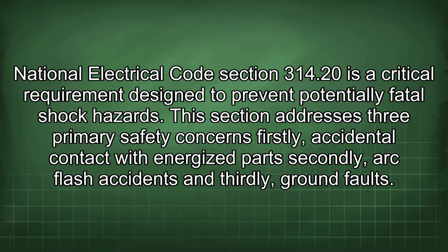National Electrical Code Section 314.20 is a critical requirement designed to prevent potentially fatal shock hazards. This section addresses three primary safety concerns. Firstly, accidental contact with energized parts. Secondly, arc flash accidents. And thirdly, ground faults.